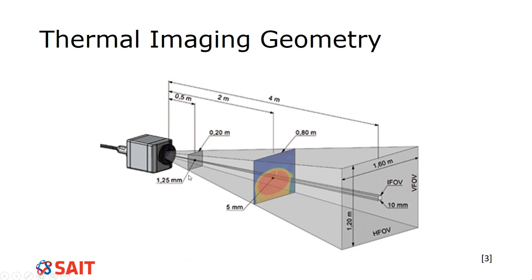So the negative of the image is down here, so you can see how it's progressively reducing as it goes. And notice that it is at a straight angle. Using thermal imaging, you have to have it straight on. Otherwise, you may end up with some sort of bias at different angles. It is difficult to do, especially when you're dealing with a house and you're trying to get images from a house at like ground level.